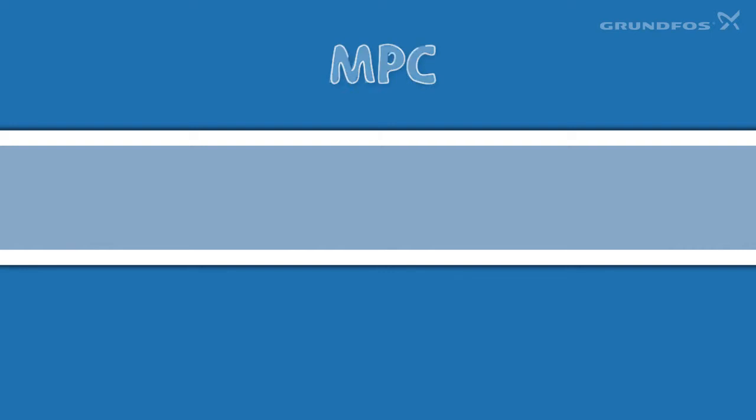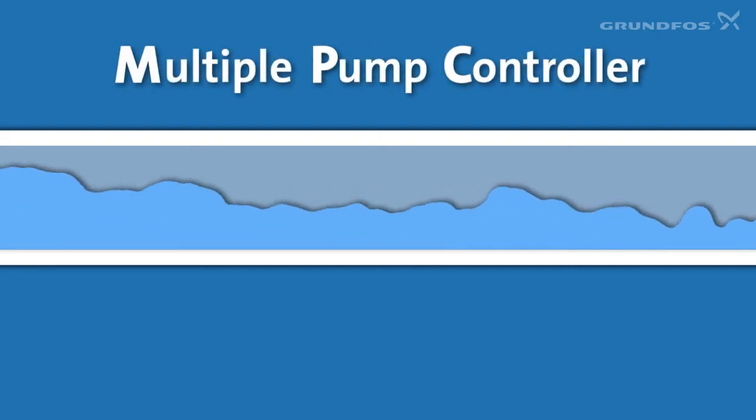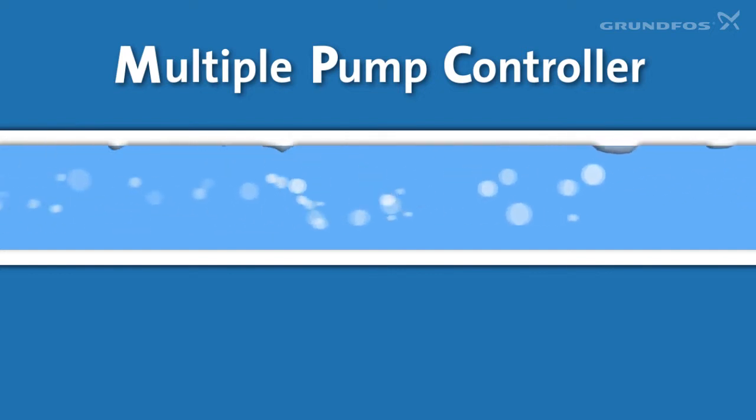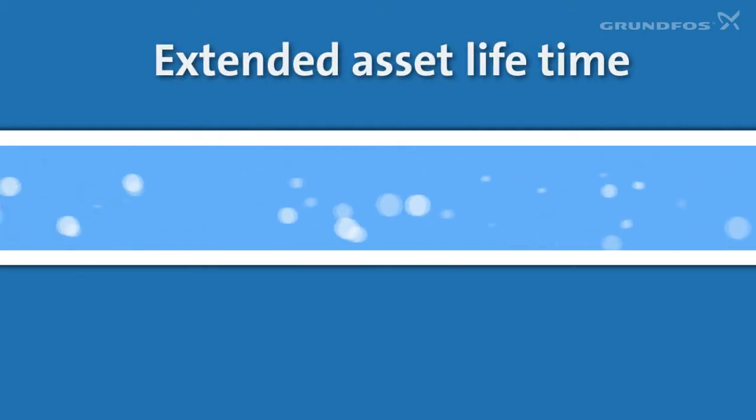Demand-driven distribution also reduces water hammer in other ways, for example by the soft build-up function. If pressure drops in your system during a pump stop, the MPC unit will slowly rebuild the pressure. In fact, the system fills up the pipes before it builds pressure. This is much gentler on the pipes, so you achieve fewer pipe bursts, reduced repair costs, and extended asset lifetime.